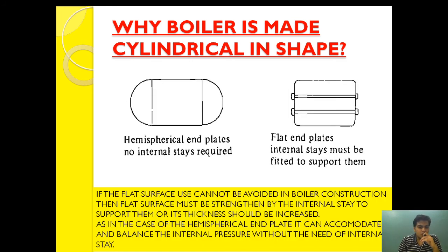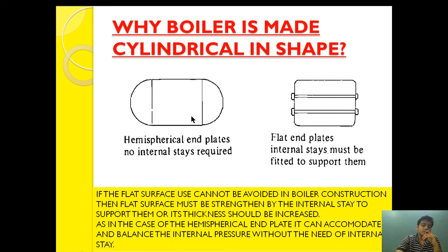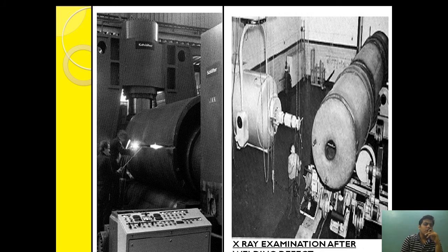Increasing the thickness too much leads to poor heat exchange, unwanted increase in weight, and increased material cost. So it is better to provide stays. The hemispherical end plate can accommodate and balance internal pressure without the need for internal stays. Hemispherical or cylindrical end surfaces don't require any stay because they can balance the force without internal stays.